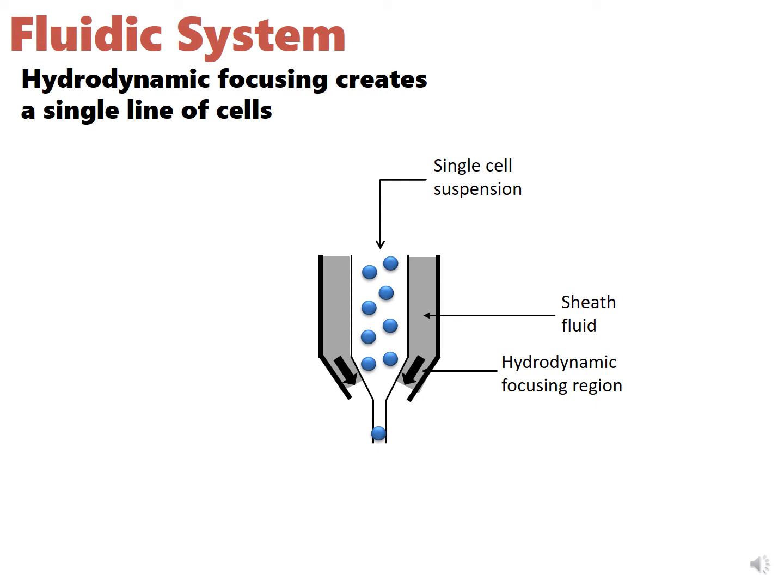The fluidic system is made up of a central core through which sample fluid is injected. This is enclosed by an outer sheath fluid. Both of these fluids are pushed through the system at slightly different pressures. Since the sheath fluid is under a higher pressure, it moves faster, creating a drag effect which will cause the sample in the central core to narrow. This process is called hydrodynamic focusing and results ultimately in a single line of particles.